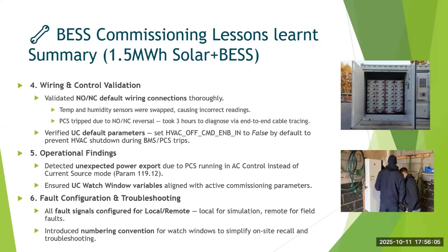The other one is the logic we use and also the control wiring we have between the BMS and PCS. If we don't have proper wiring, then it leads to a lot of challenges. One of the problems I faced: we had given the drawing properly for connecting the NO/NC contactors to the PCS from the BMS. Unfortunately, when the technicians were connecting it, they connected it in the opposite way.